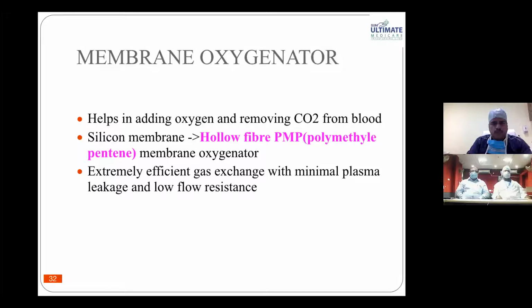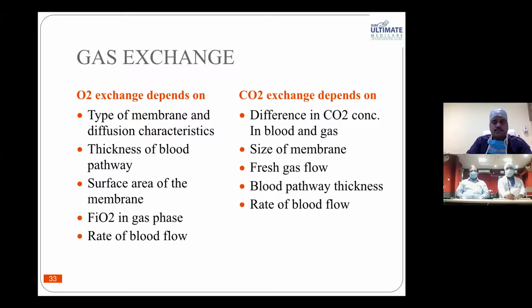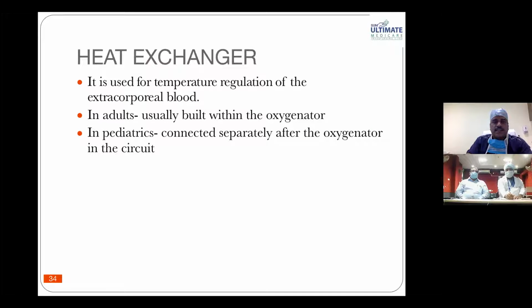The membrane oxygenator used is a hollow fiber polymethylpentene membrane oxygenator. But in the heart-lung machine, in CP bypass, we use a simple membrane oxygenator. Here we use PMP membrane oxygenators. It's extremely important to know about this because a regular membrane oxygenator we cannot use in ECMO. This is very costly. The heat exchanger is a very important component of ECMO because the blood is coming out of the body, getting circulated outside at ambient temperature and returning back to the body. Definitely the temperature will go down. We have to maintain the heat. So every ECMO machine will have a heat exchanger mechanism by virtue of which to maintain the temperature of our body. It is very important.